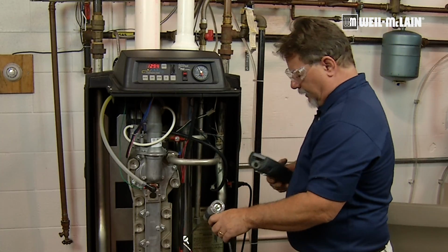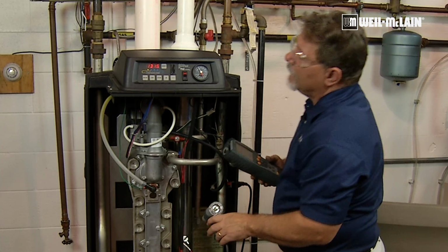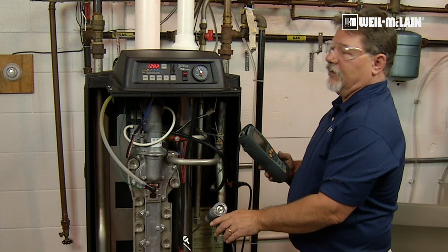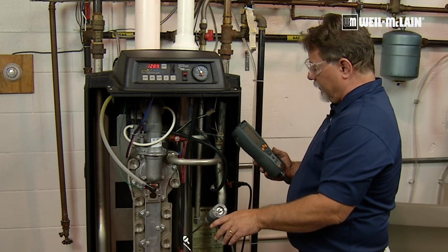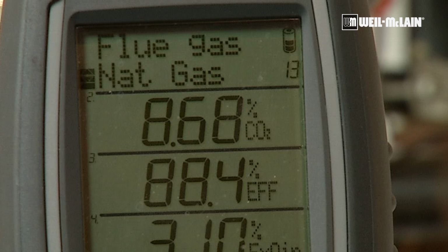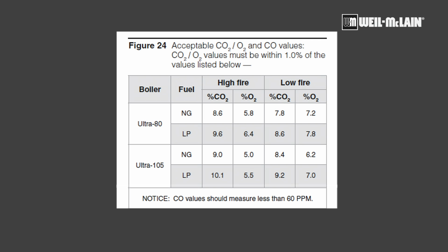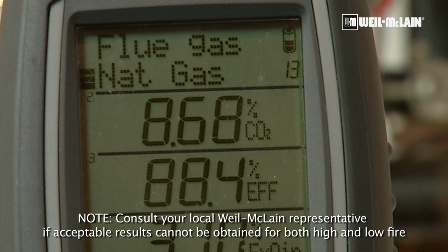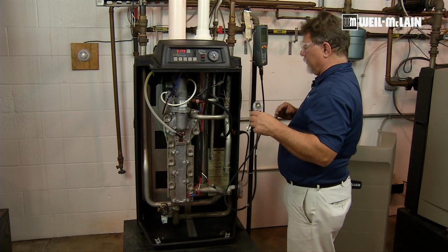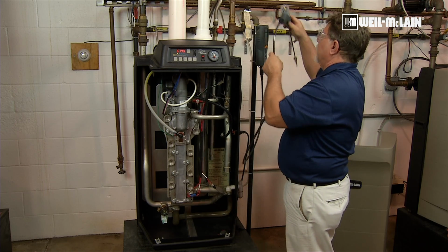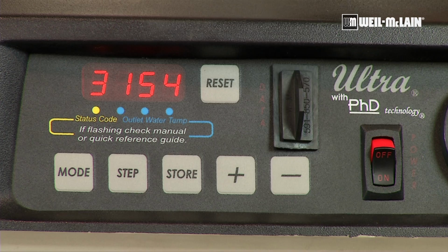I'm going to go look at our combustions again. Now verifying still the fan RPM at low fire. Okay, I'm reading 8.68. The target is 8.4%, but I'm happy with that reading. Again, the book says plus or minus 1%. So what I'm going to do is pull my probe out, let it cool down, and restore the boiler to normal operation.